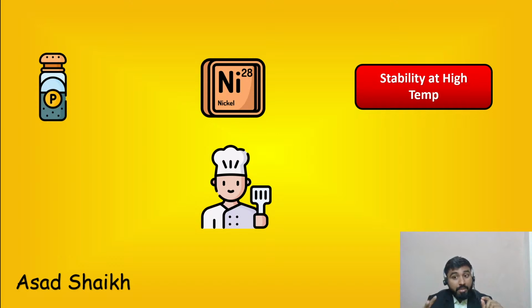At very high temperatures, I'm talking about something like 600 or 800 degrees, there are certain applications which require such temperatures. There you have to be very cautious with dissimilar metals. I would recommend the same material, because with dissimilar metals at such high temperatures you can have extra stress, which can cause the stem to break, or some other issues can happen in the plant.